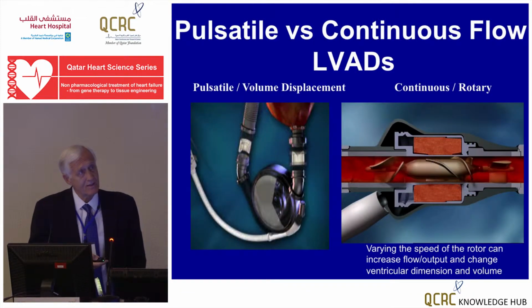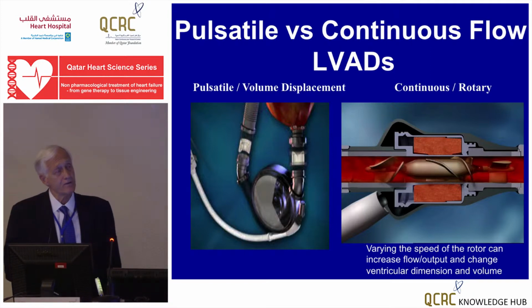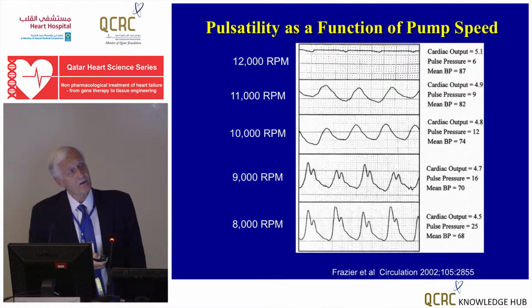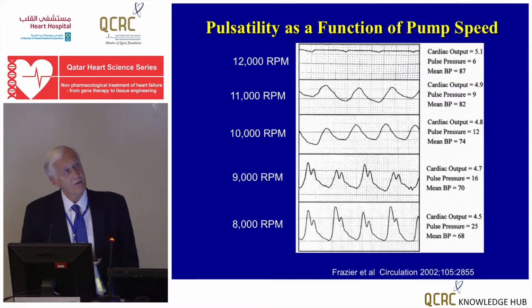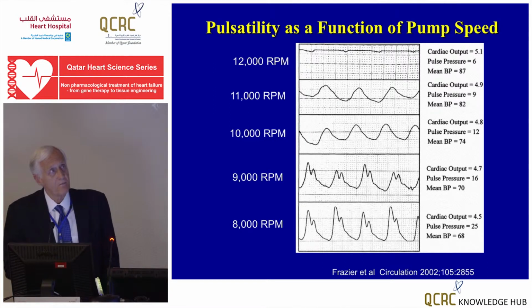This pump also has a single moving part, which is the rotor, which draws blood on a continuous basis and propels it back into circulation in a non-pulsatile manner. This, I think, really gives you a fairly good sense of, here's the arterial pressure tracing as the device is being initiated, and the speed, which is directly correlated with the amount of draw and blood removed from the LV apex. And you can see that the arterial pulsatility goes down and down until you're at full speed, in which there really is no pulsatility at all.